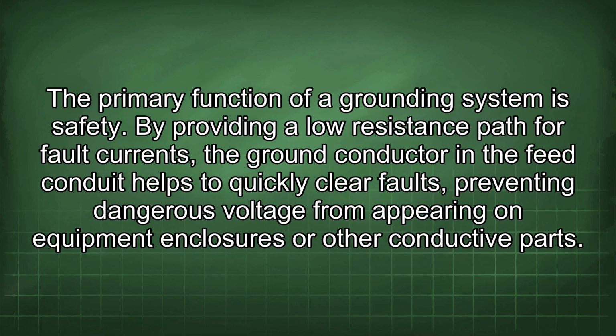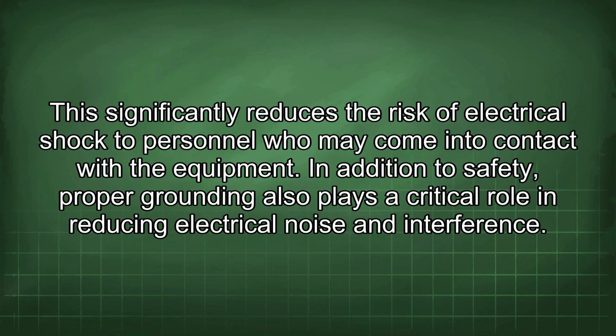The primary function of a grounding system is safety. By providing a low resistance path for fault currents, the ground conductor in the feed conduit helps to quickly clear faults, preventing dangerous voltage from appearing on equipment enclosures or other conductive parts. This significantly reduces the risk of electrical shock to personnel who may come into contact with the equipment.